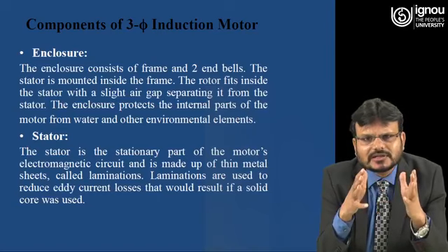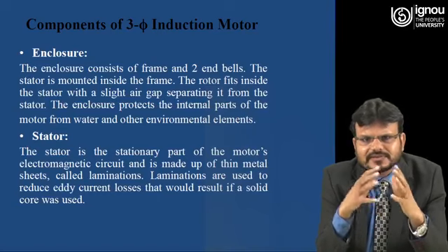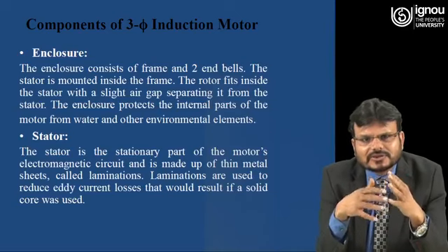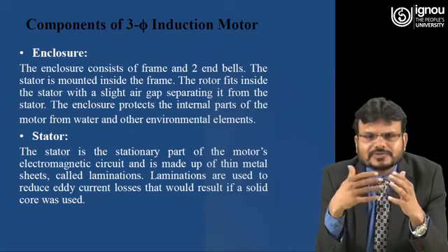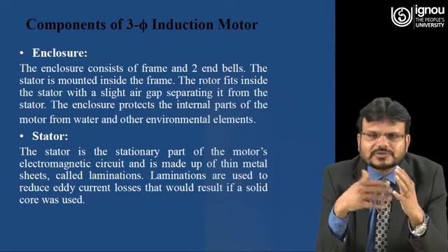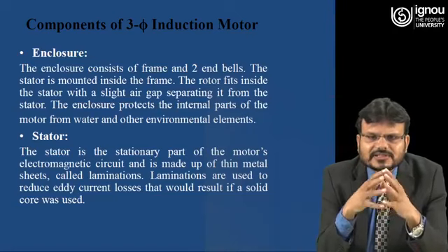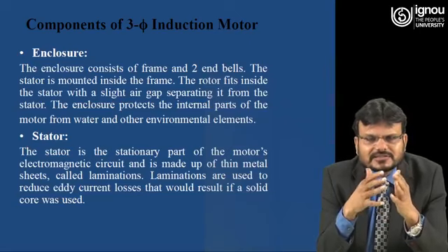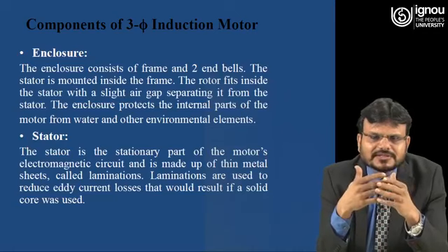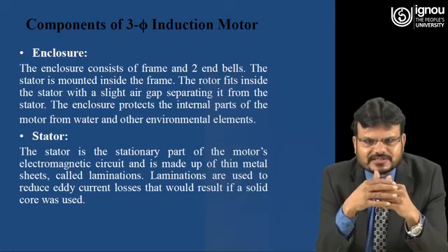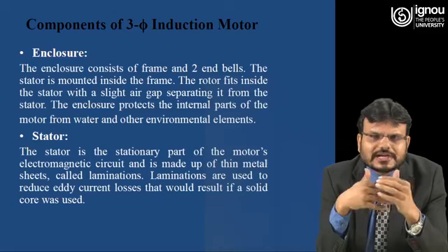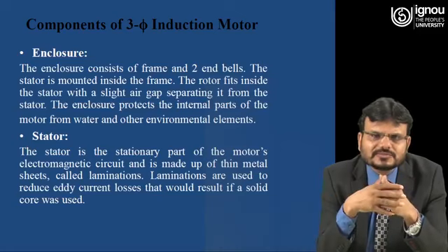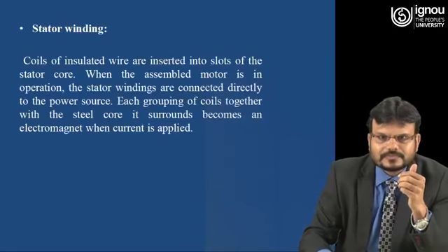The next part of the induction motor is the stator. The stator is the stationary part of the motor's electromagnetic circuit, and it is made of thin metal sheets. What is the use of these thin metal sheets? By making this lamination you can reduce the eddy current losses. If you are able to reduce the eddy current losses, you are able to increase the efficiency of any machine.